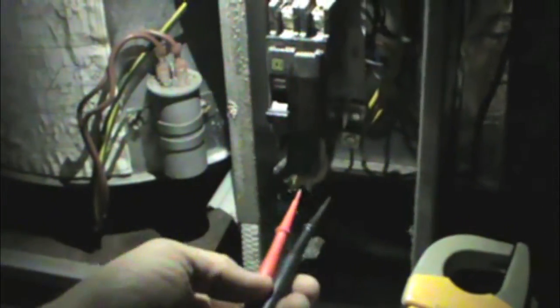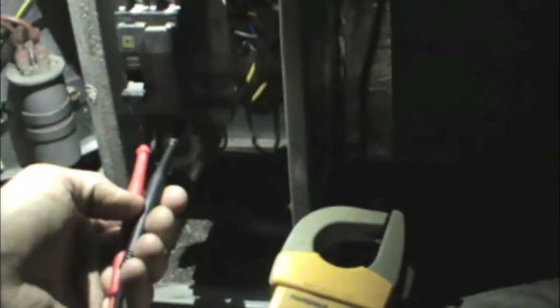So turn it back on, and it's always a good idea to reset the breaker. You know, breaker could be having a problem if you don't have any incoming voltage. Well, outgoing to the unit out of the breaker if you have incoming voltage. So we're going to check here. So we got 247 coming in, and we got the same coming out, so we know we're good on that. The next question is why is our thermostat not coming on? Thermostat could be faulty if we have 24 volts going to it.